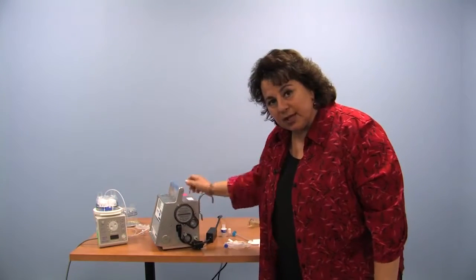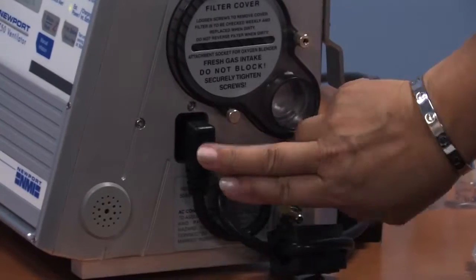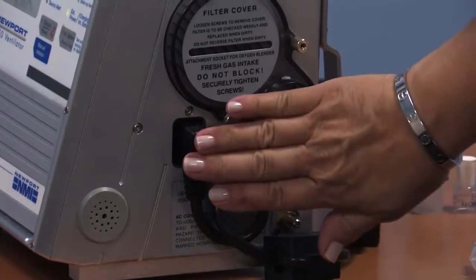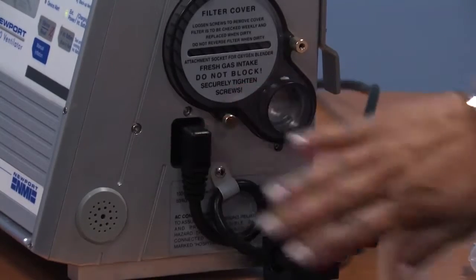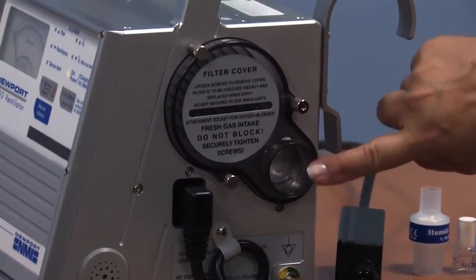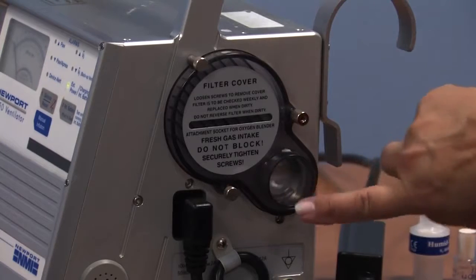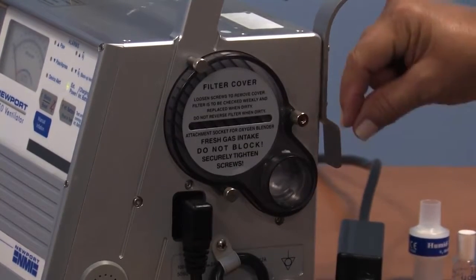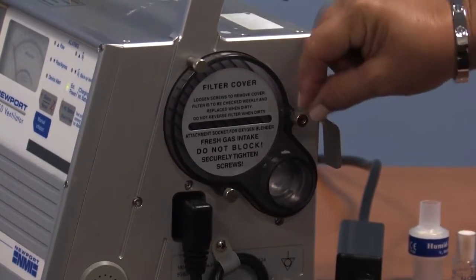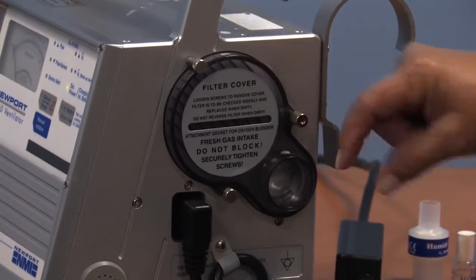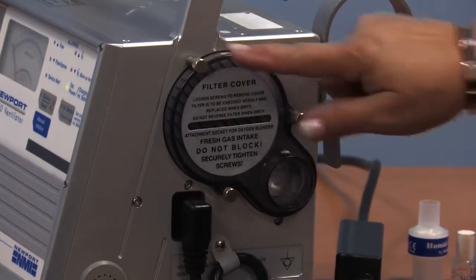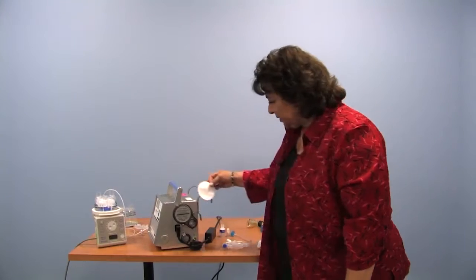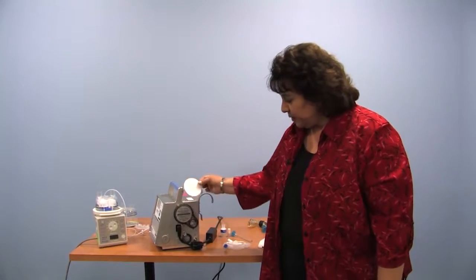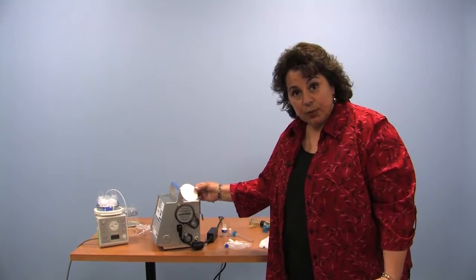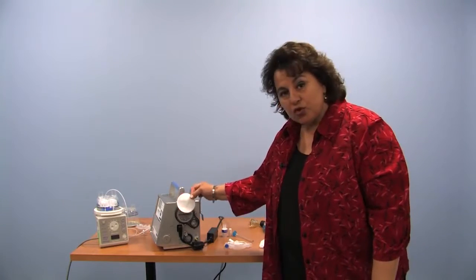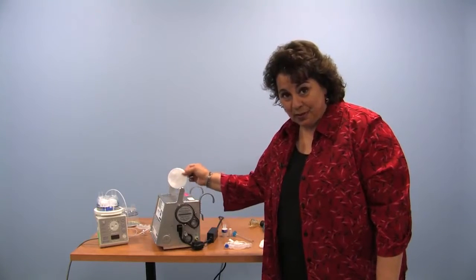The other side of the machine here has the power connector for when you're not on battery and you're charging the battery or running off wall power. The gas inlet is here. When you look in there, it's kind of hard to imagine that air does go in this hole, but if you hold a tissue to it while it's in operation, you'll see the tissue being pulled in. If you remove these three screws, what you'll find is an inlet filter. So periodically, per your durable medical equipment company, please do check and change the filter. It should be white.